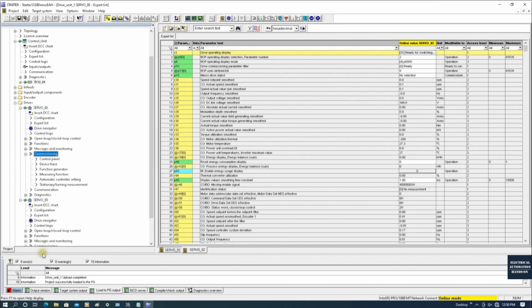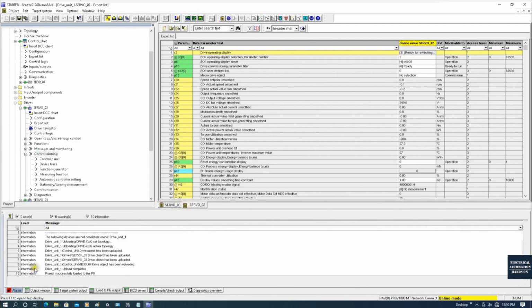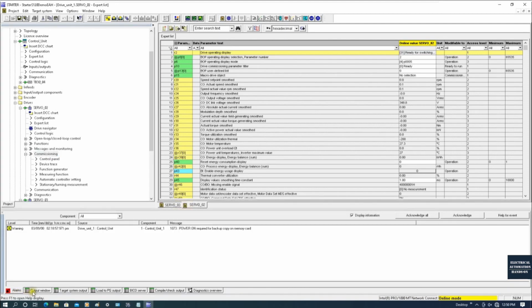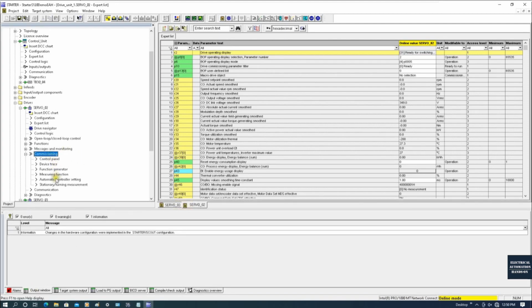And next step, probably we can use the commissioning function from the Starter software, and we can power on the motor, and we can jog or control the velocity of this motor. So we can verify the hardware of the motor is correct. And also we verify if all the configuration we just did is correct. This paves the way for the further motor tuning. And we can verify the motor direction, and we can also verify if the encoder value makes sense.